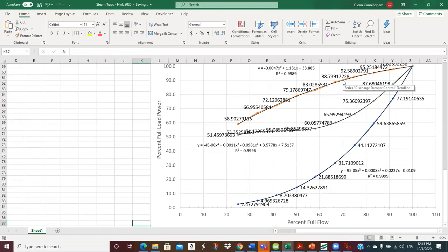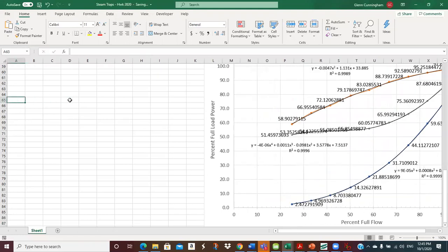That's right on 90% full load power, okay? That's with dampers. If you did this with VFD, I don't know, what is it? There's 40, I don't know, 37, 38%, something like that, however you want to read that. And then I pulled those numbers.